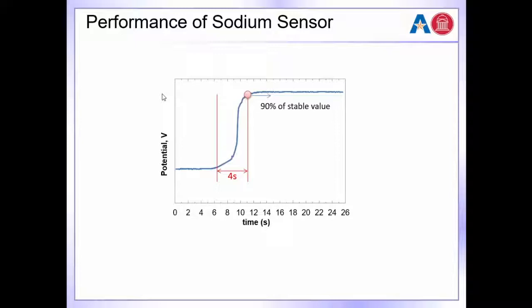In our pH sensor, we demonstrated more than 3 years, and we always have a transition time that's shorter than 1.6 seconds. So we were wondering, if the sodium sensor behaves very slowly, then that defeats the purpose of having a sensor. So we also measured the transition time of the sodium sensor, and we found the sodium sensor reaches 90% of the final value at 4 seconds.